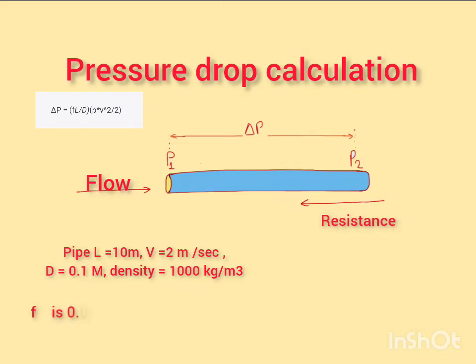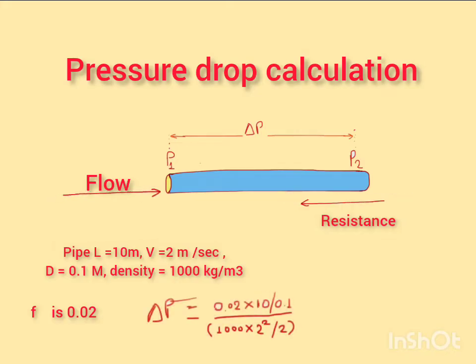Using the formula we just discussed, we can calculate the pressure drop as follows. Delta P equals 0.02 times 10 divided by 0.1 times 1000 times 2 squared divided by 2. Delta P equals 4000 pascals. So the pressure drop across the pipe in this example is 4000 pascals.